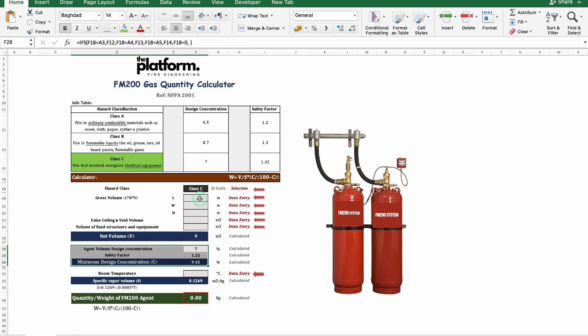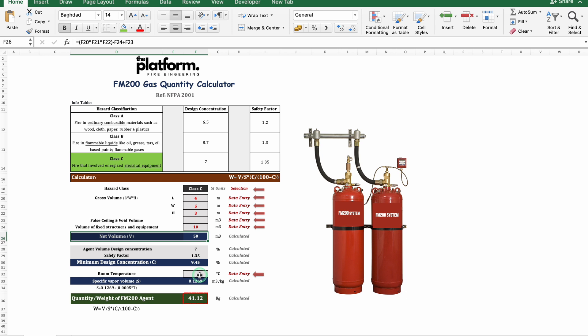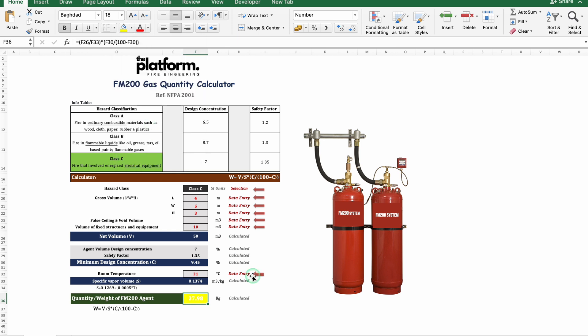Now you will need to enter the room dimensions and the fixed structure and equipment volume to get the net volume. We now have the calculated volume and the design concentration. By entering the room temperature you will get the specific vapor volume. The final result is now ready, which is the required quantity of FM 200 gas in kilograms.